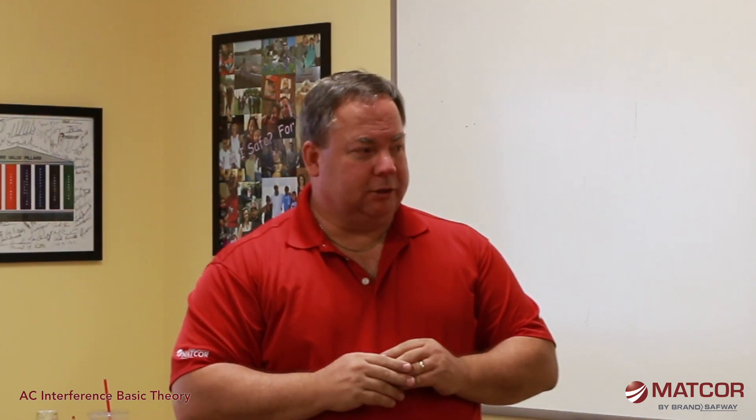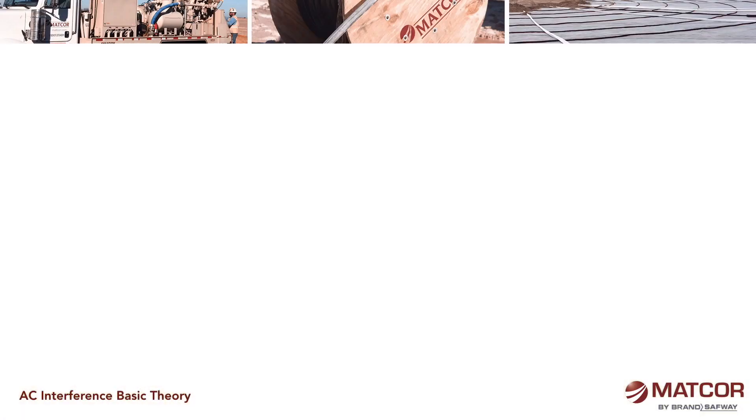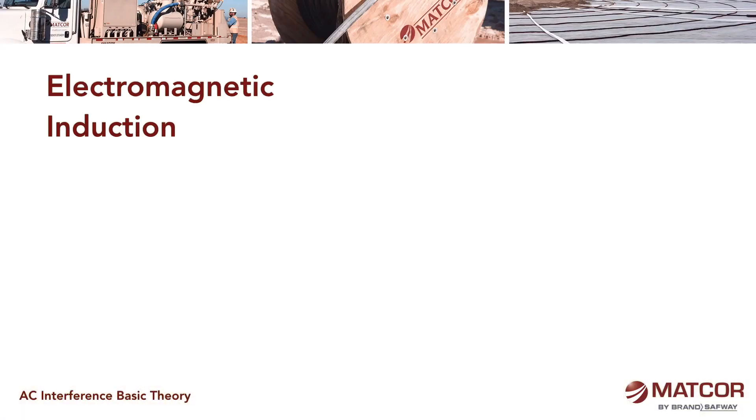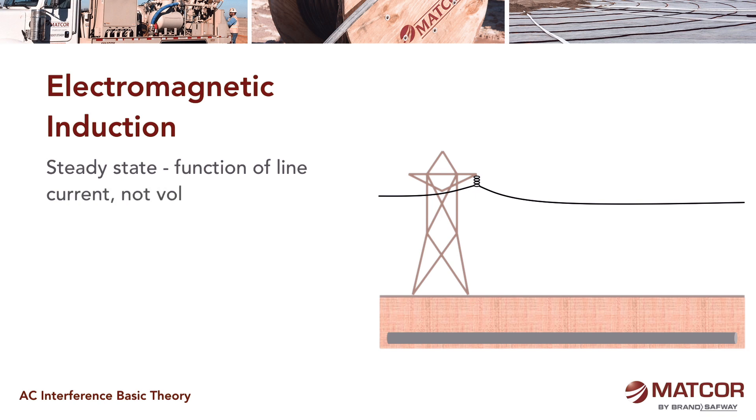The second interaction or interference concern when it comes to pipelines and high voltage lines is electromagnetic induction. Conductive coupling occurs during a fault — it's a rare event, may never happen in your lifetime in the area you're concerned about, or it could. But electromagnetic induction, on the other hand, is pretty much a steady-state thing. If there's current flowing through the line, you're going to have some form of induced current flowing in the pipeline.